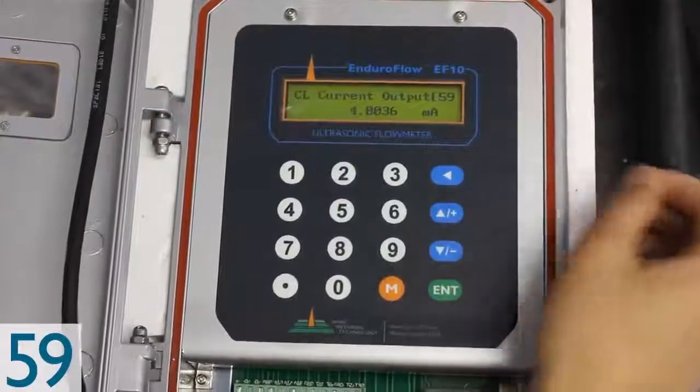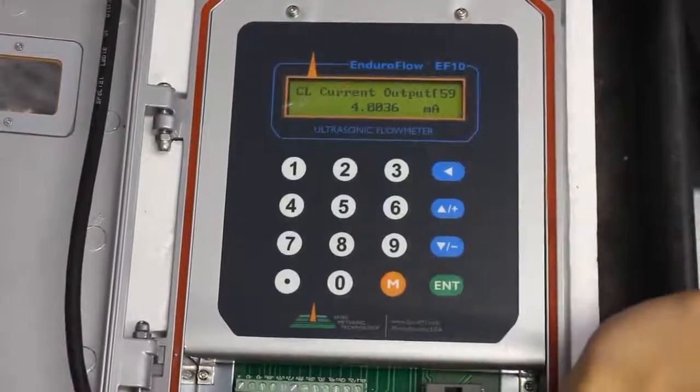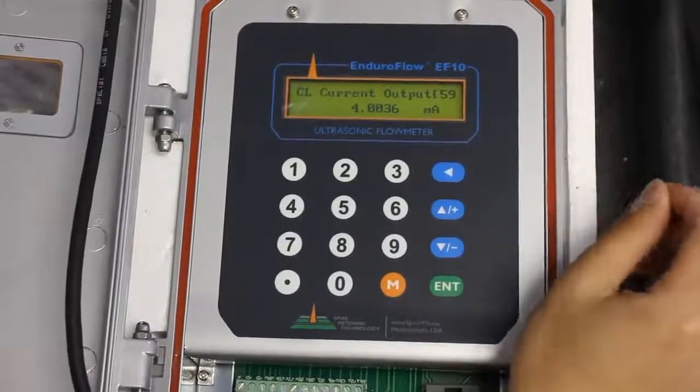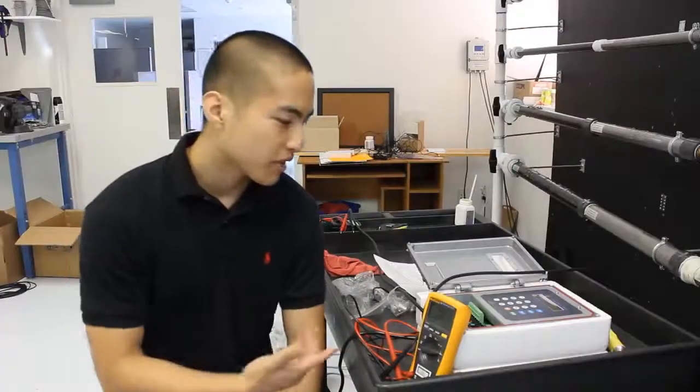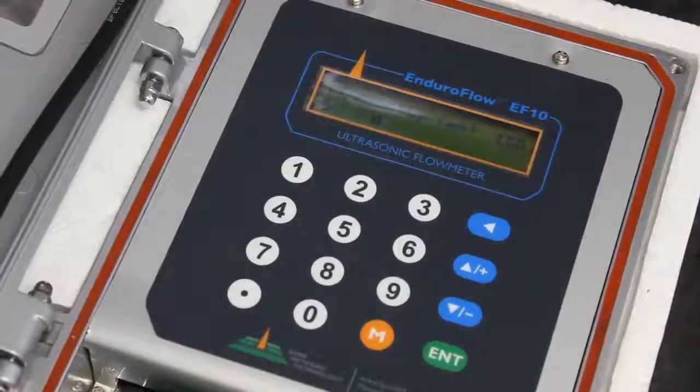So now we're going to talk about how to manually test the 4-20 milliamp and make sure it's functioning correctly. Right now I'm at menu 58. And we can scroll through to display different values of the milliamp. And what we're going to try to do is to match the values on the screen to the values that are going to be shown on this multimeter.